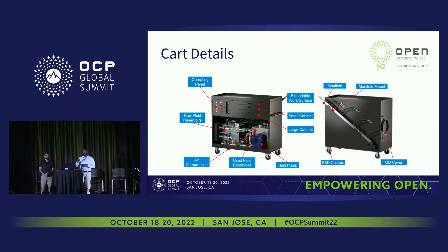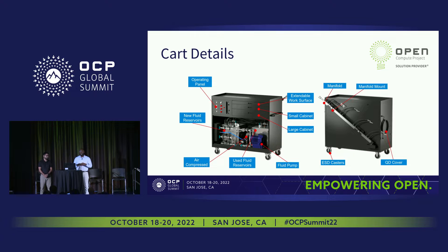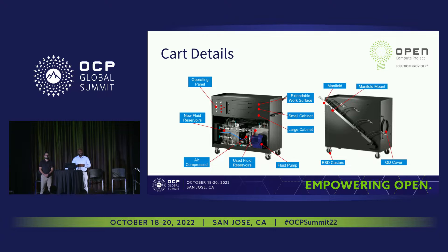Looking at the front and back view of the cart: on the front left side, you can see our operating panel, where the user will control the cart and all of its functions. We have an extended work surface, which allows the techs to have additional room to service their equipment. We have a small cabinet for any gear the techs might have — small tools, multimeter, et cetera — and a large cabinet with our auxiliary hoses for all of our fluid cycles. On the bottom, you can see our reservoirs: both a new and a used coolant reservoir, to avoid contamination of fluid when filling or draining a rack. We also have our compressed air pump and fluid pump inside the cabinet. On the rear, there's a manifold mount, making servicing of the AALC racks easier since the manifolds are large and heavy, along with ESD casters on the bottom and a cover.